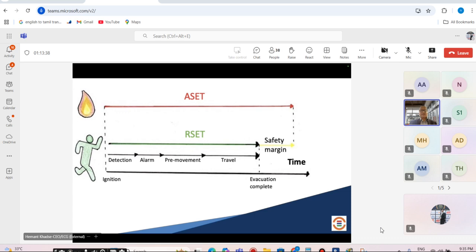So the performance-based standard has a very clear mandate. NFPA 101 has addressed it. The SFPE manual also addresses how this can be achieved using simulation techniques, where you can define your available safe egress time, ASET, and your required safe egress time, RSET. It's a very engineered way to show that your RSET is lower than your ASET. That's the objective of life safety, so that you ensure the egress is safe for any person of any impairment, of any gender, in that particular building. There is no cast-in-concrete rule for a specific minimum RSET. NFPA 1 has a general statement of not more than 8 minutes, but it depends on the building.